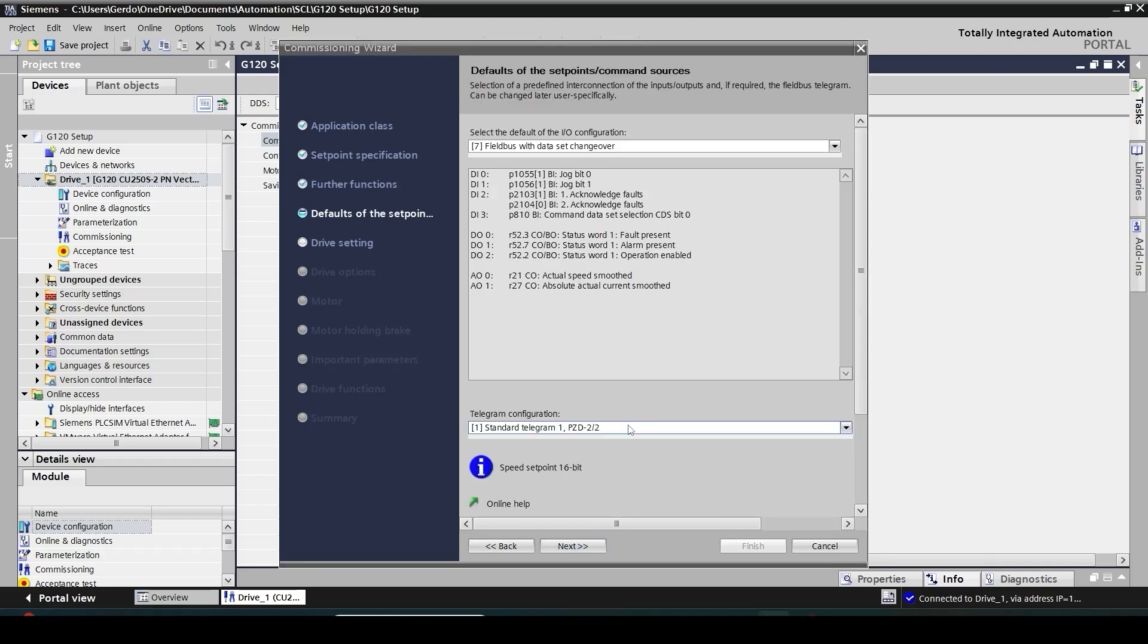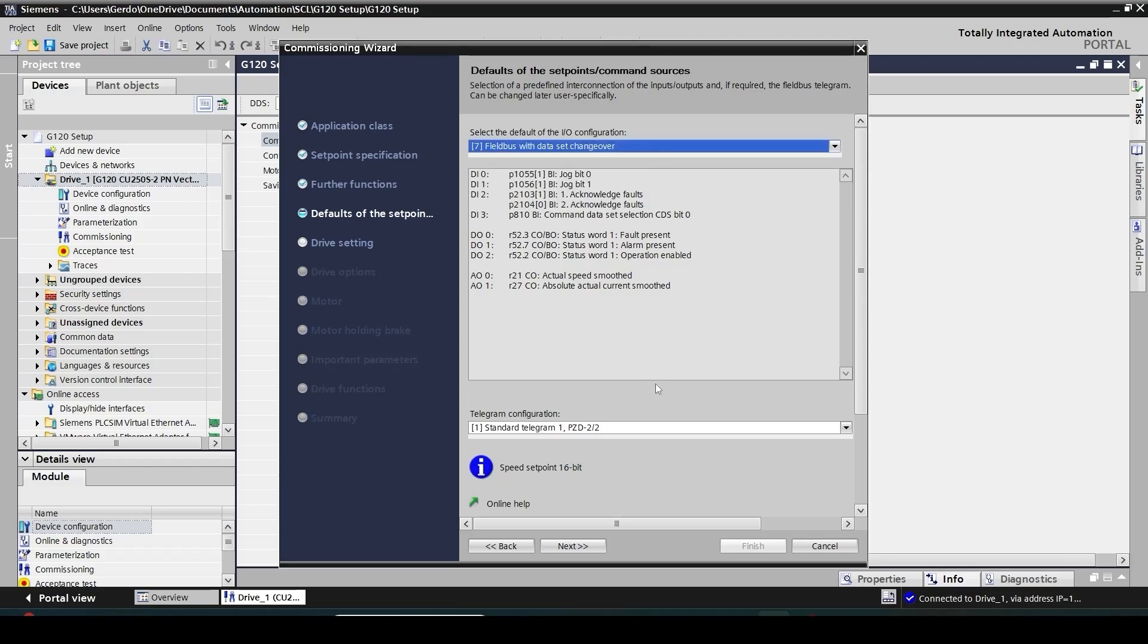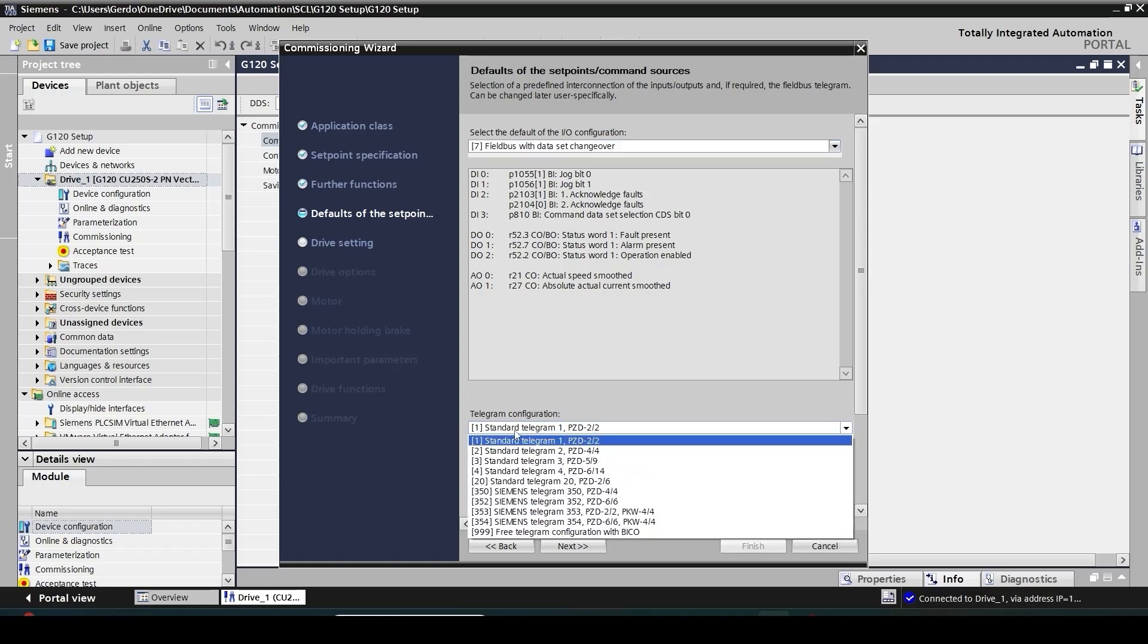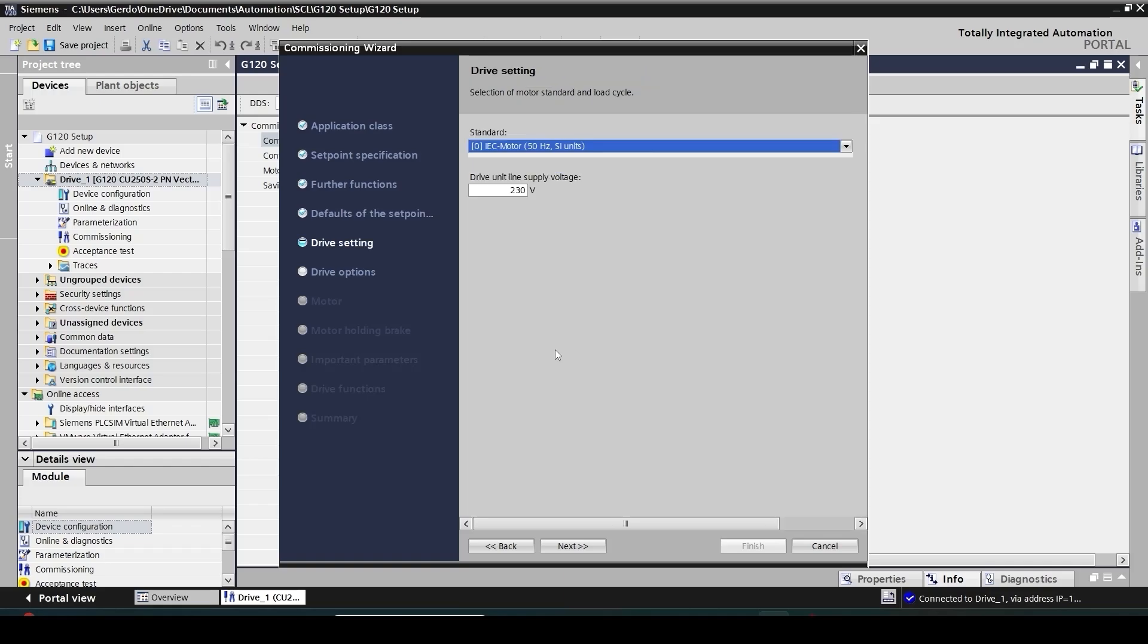Next question is about how to control the drive. Basically how to send command and receive feedback. You can either do it from the built-in IO on the drive or you can do it through an Ethernet telegram. The default option is that you have both choices and you have the option to toggle between hardware IO connection or Ethernet option. That's the item number seven, field bus with data set changeover, and if it's going through the network it's going to go through standard telegram one which is the most popular option. As you can see here there are a couple of inputs for jog, acknowledge, fault reset, and then some output for alarm, fault, and operation enabled.